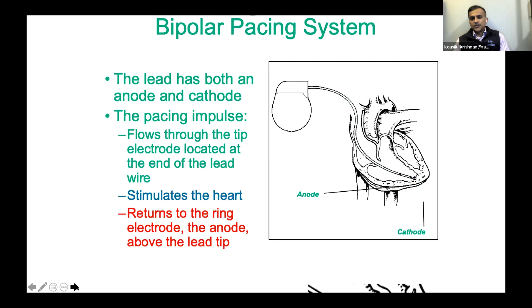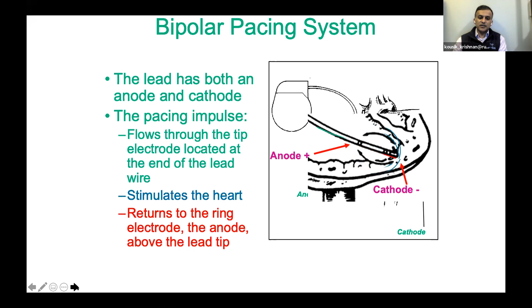So that's the circuit. In a bipolar pacing system, the cathode and anode are geographically very close to each other. So the circuit is between the cathode and the anode, which is usually only a centimeter or two behind, or less, behind the cathode. So the location of that circuit is very discrete and geographically in a close area. And so when the can is not needed for the circuit, you can take the can out of the pocket and there won't be any loss of pacing. And because the antenna is much smaller in size, something that is much further away from the heart muscle is less likely to be sensed and lead to inappropriate inhibition of pacing.